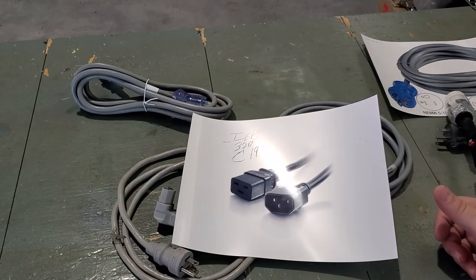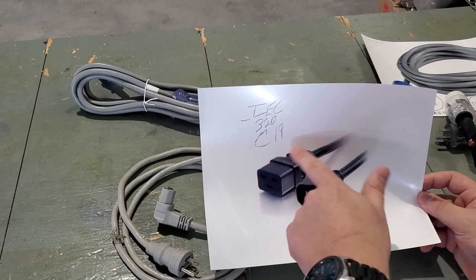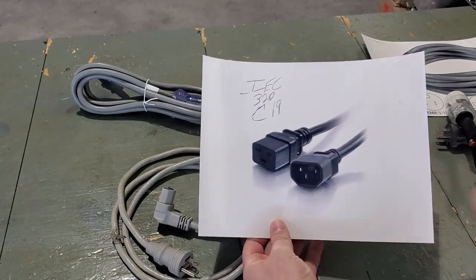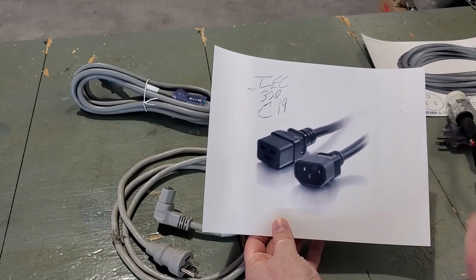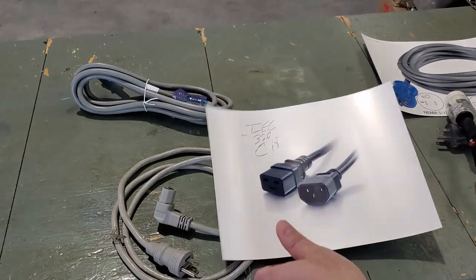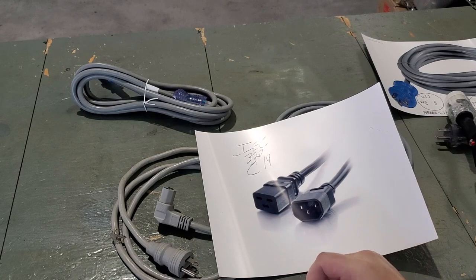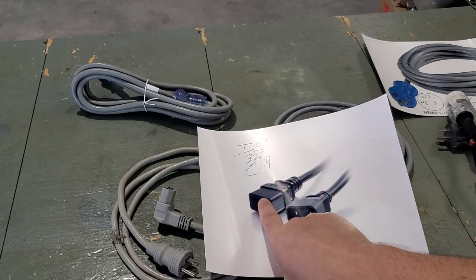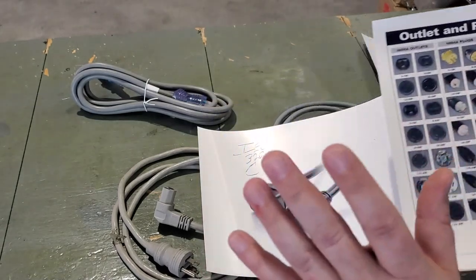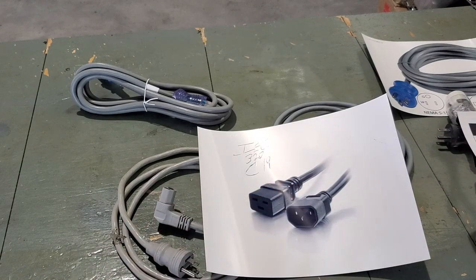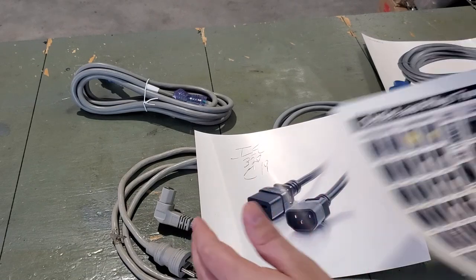There are always exceptions to the rule, and one of those is going to be the IEC 320-C19. This square plug end is found on some medical devices that are going to pull more amps. Manufacturers sometimes do this to make the cord proprietary. If you know what you're looking for — like an IEC 320-C19 — it makes it much easier to find the cord. For example, a Belmont FMS 2000 rapid infuser has one end that is the C19 connector, and the other end is either a 5-15P or a 5-20P. Instead of spending $150 for a cord from the OEM, all you need to know is the correct terminology: you're looking for a 5-15P to IEC 320-C19. You'll find that cord on Amazon.